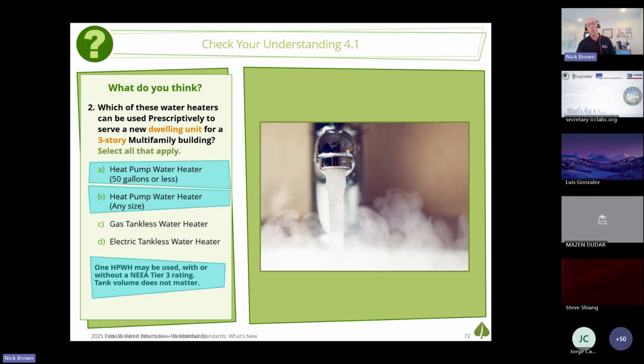Any size heat pump water heater is allowed prescriptively, but what isn't allowed is the gas tankless water heater serving individual dwelling units, low-rise multifamily. That's a change for 25, so that's why we put this question in here. Remember, high-rise multifamily with 4 habitable stories or more, you can still use individual gas tankless water heaters.